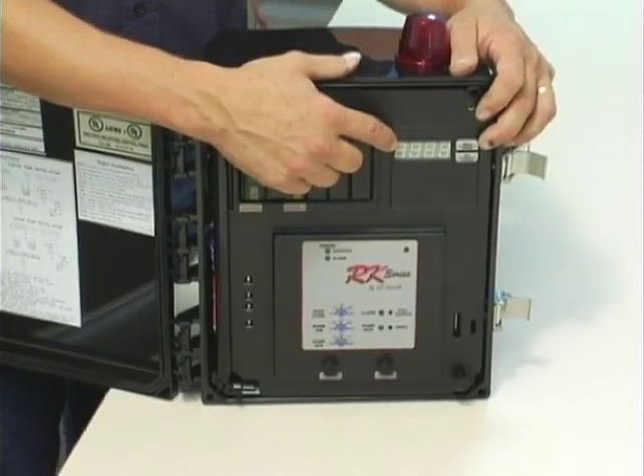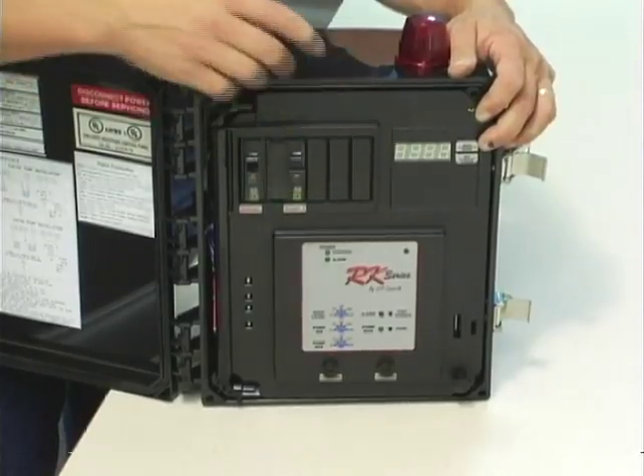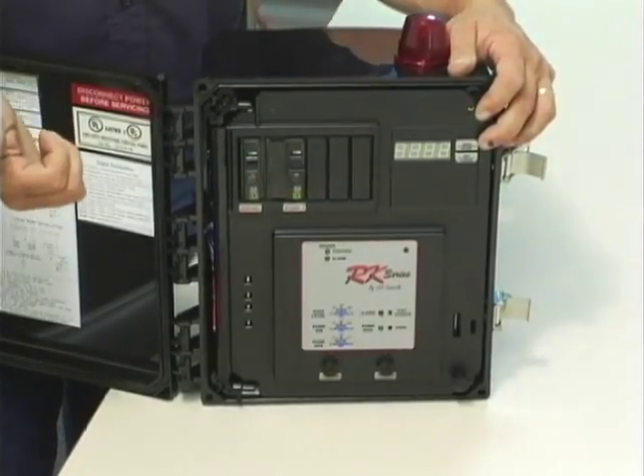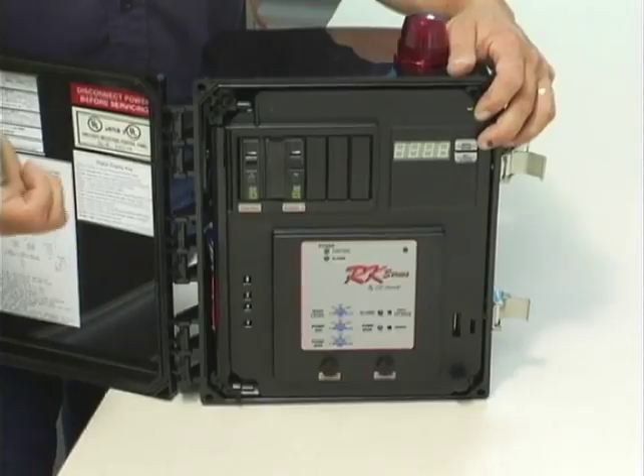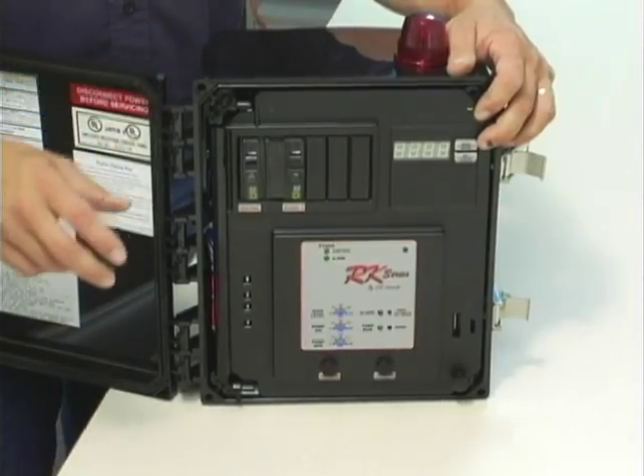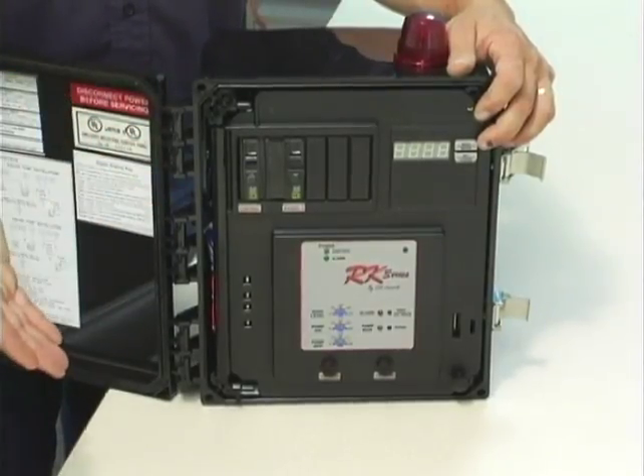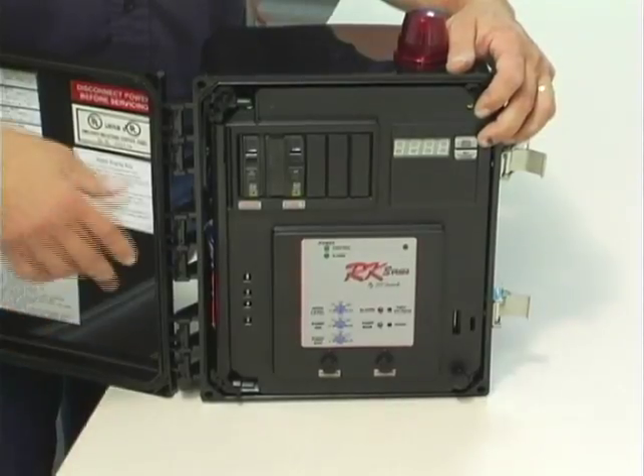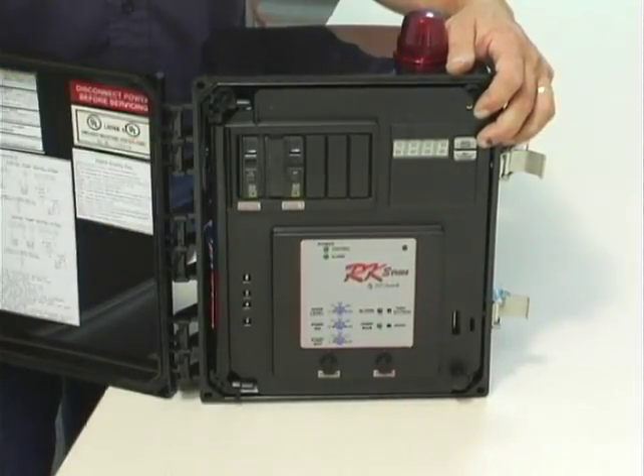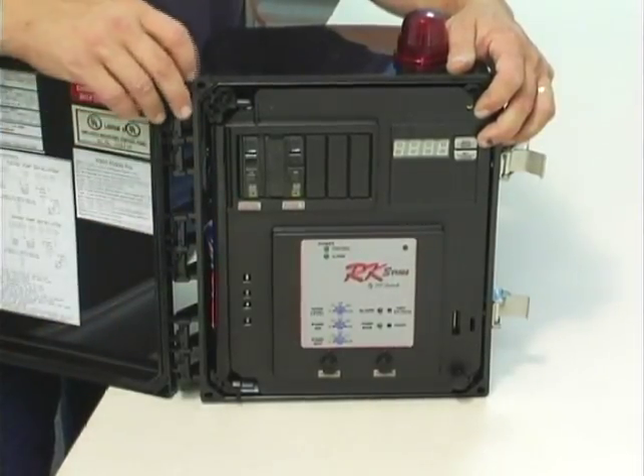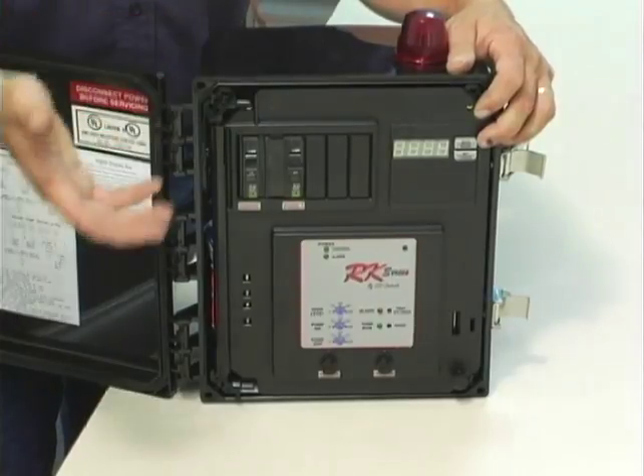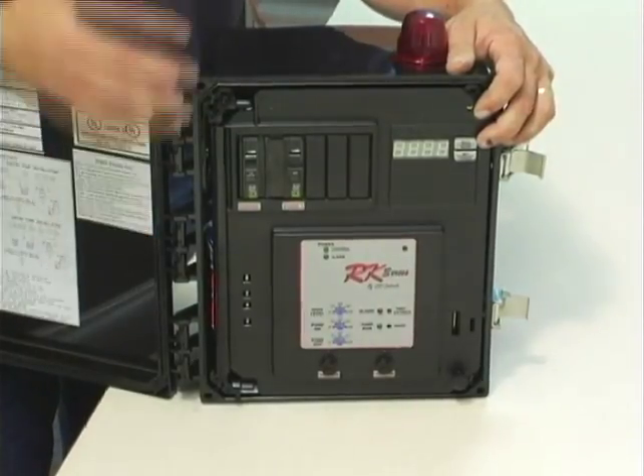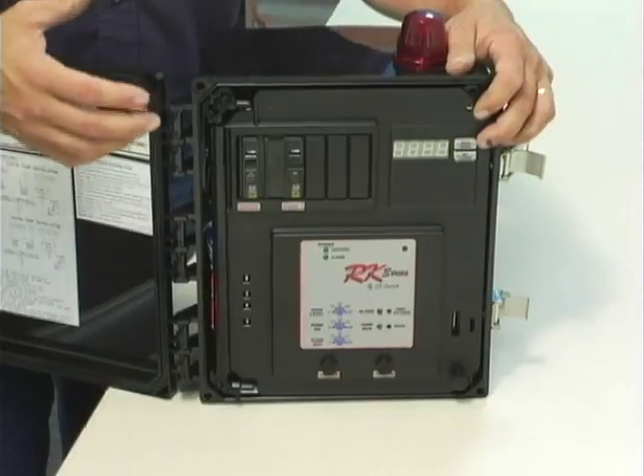If it's reading 0, then that means one of two things: the control panel has lost pressure in the tubing between the panel and the pressure bell, or there is no water in the tank, it is pumped all the way down. So first thing you would do is open the tank, inspect to see how much water is in the tank. If there isn't any water in the tank, then you need to test the pressure bell on a 5-gallon bucket of water or something like that to test it.